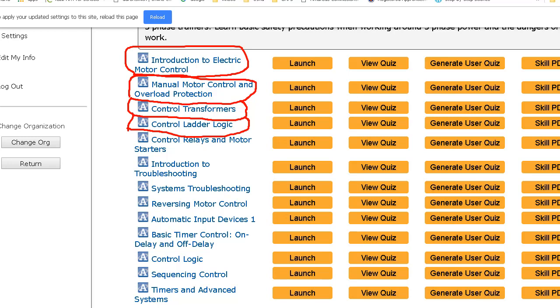Remember the difference between, remember I talked about the NEMA style overloads and the little solder that melts inside the tube that allows the little gear to change. So remember that portion. Remember how magnetic overloads work. So we have like a little coil floating in oil and a little valve to let the oil pass through, and so we can actually delay those magnetic overloads, those dash pots. That allows us to adjust the response time. And then of course we need to know a contactor uses a magnetic coil to open and close.